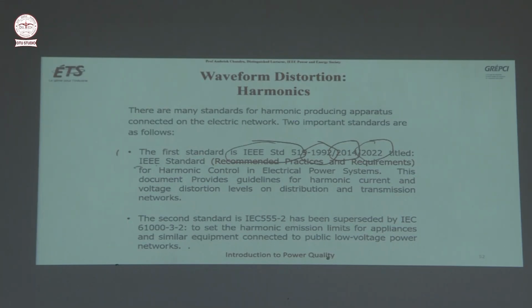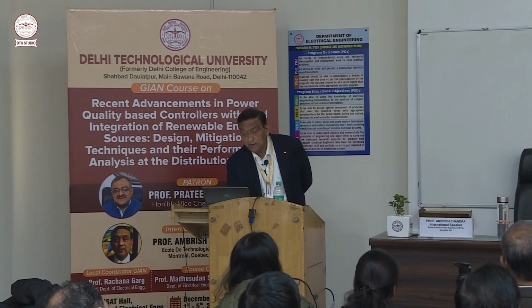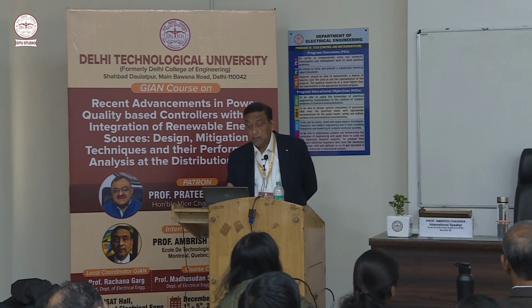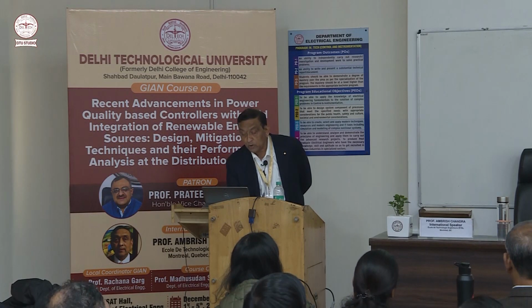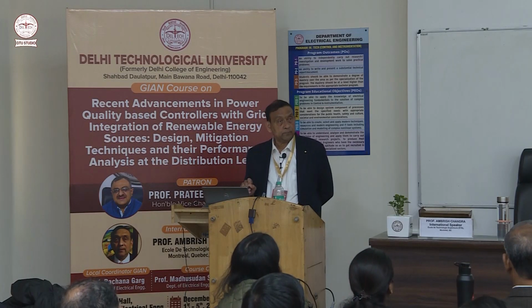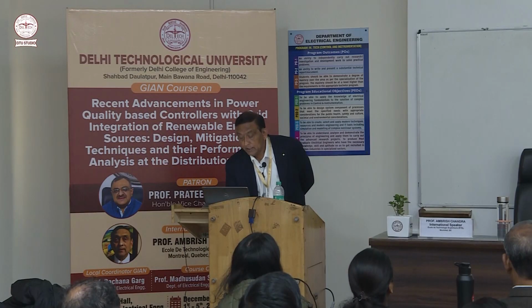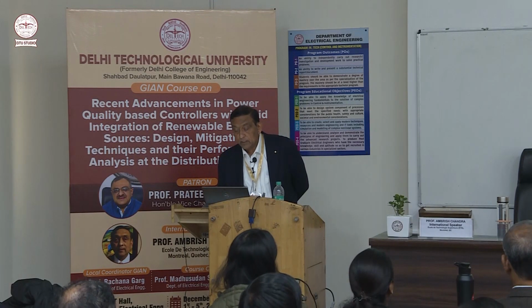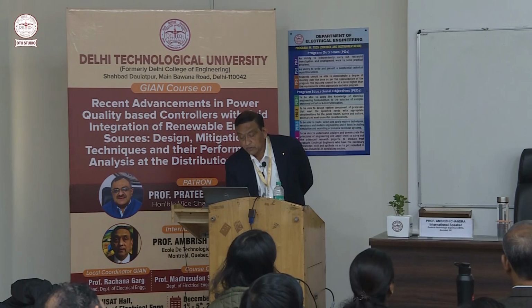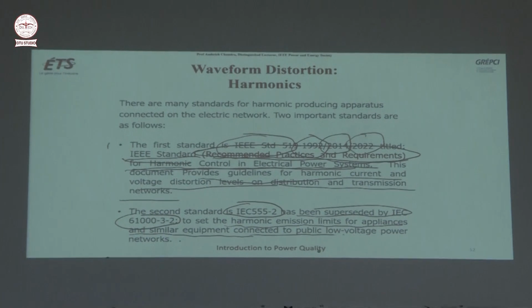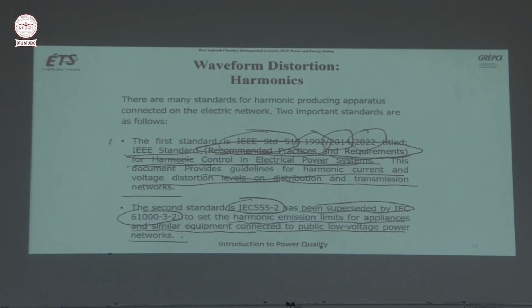So what is the title? Initially it was IEEE standard recommended practices and requirements for harmonic control in electric power systems. But later on in the modification, they dropped this term. So now I see IEEE standard for harmonic control in electric power systems. This document provides guidelines for harmonic current and voltage distortion levels on distribution and transmission networks. And there was a second standard, IEC 555-2, but it has been superseded by 61000. So this is to set the harmonic emission limits for appliances and similar equipment connected to public low voltage power networks, but this is especially European countries, they follow it. But in North America, we follow IEEE standards.